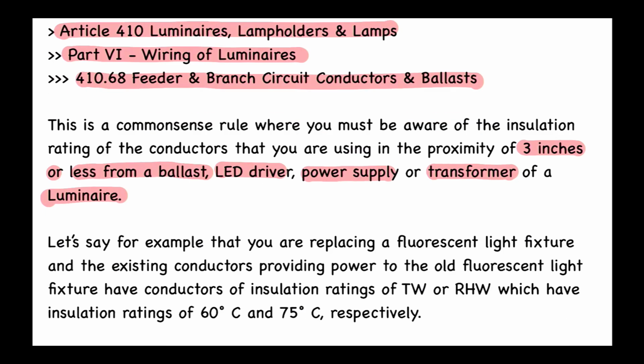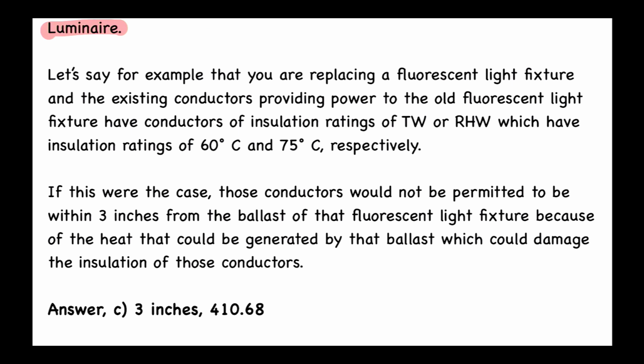of a luminaire. Let's say, for example, that you are replacing a fluorescent light fixture and the existing conductors providing power to the old fixture have insulation ratings of TW or RHW, which are 60 degrees C and 75 degrees C, respectively. If this were the case, those conductors would not be permitted to be within 3 inches from the ballast of that fluorescent light fixture because of the heat that could be generated by the ballast, which could damage the insulation of those conductors. And again, the answer to this question is C, 3 inches. And this is code reference 410.68.